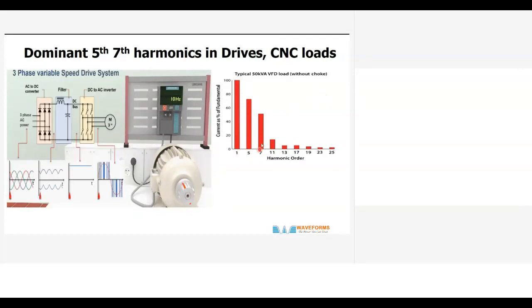You can see the system. All these harmonics are generated by the VFD. Without a choke, you'll have this effect. The harmonic magnitude of the fifth will be very high, and to a lesser extent the seventh, and similarly the 11th, 13th, and all that. And the output.